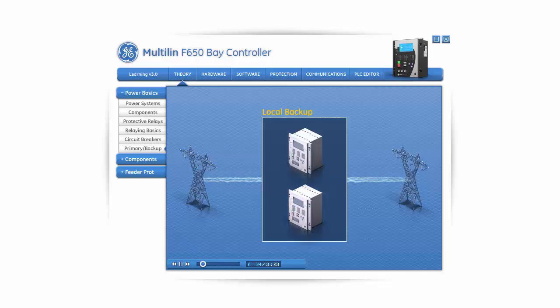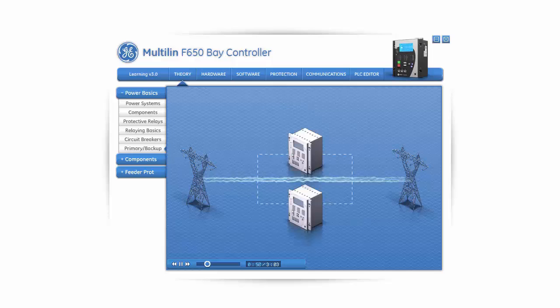This means that the relay providing the backup is located on the same component that is being protected by the primary relay. Local backup protection is often used to protect against failure of both the primary relaying system and the associated circuit breaker. The only potential drawback is that local backup relaying often uses the same CTs, VTs, circuit breakers, etc., which can fail, likely resulting in failure of both the primary and local backup relay.